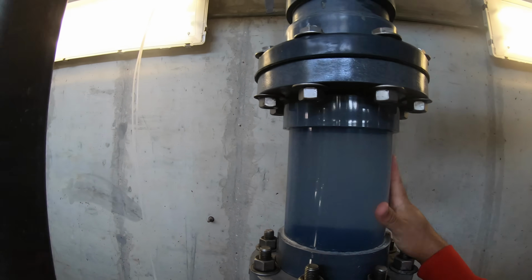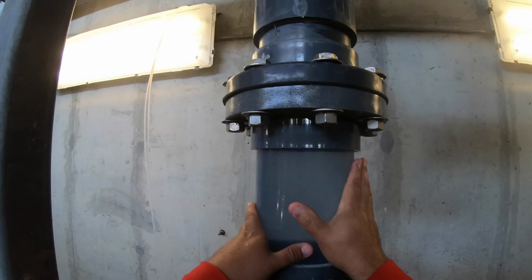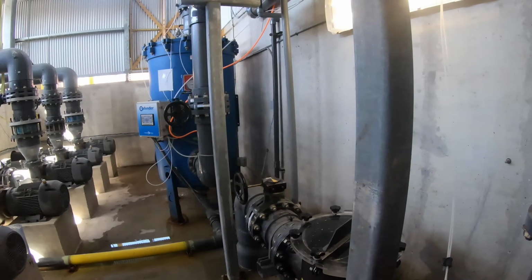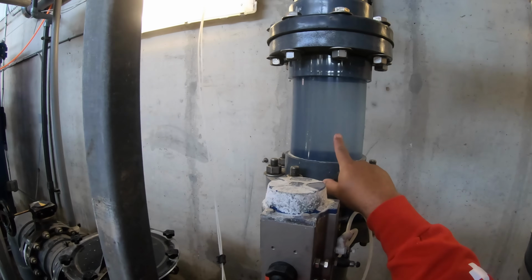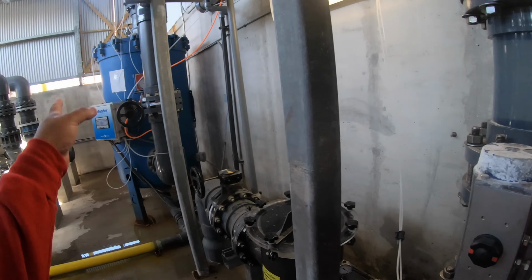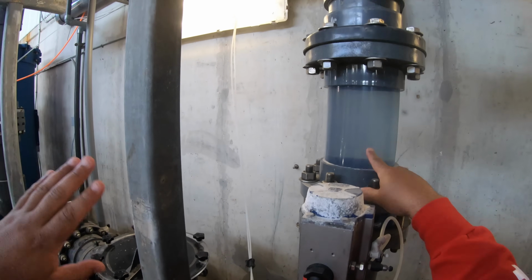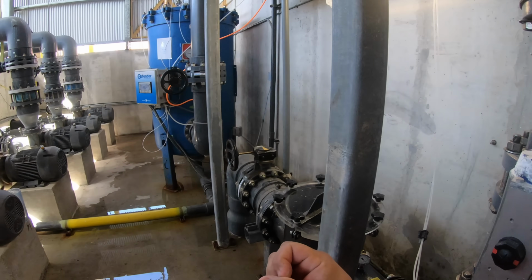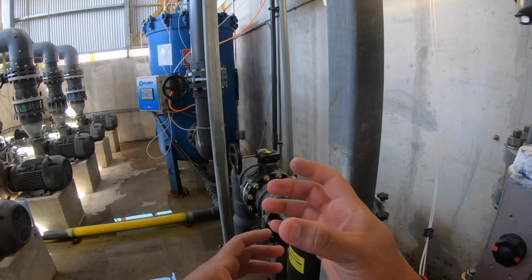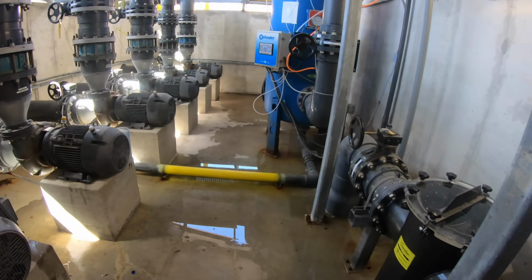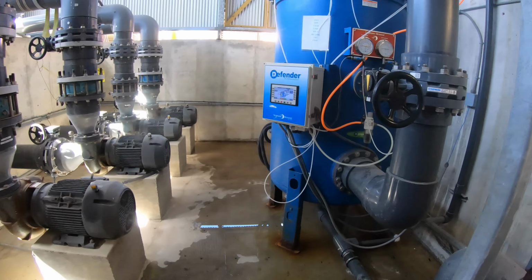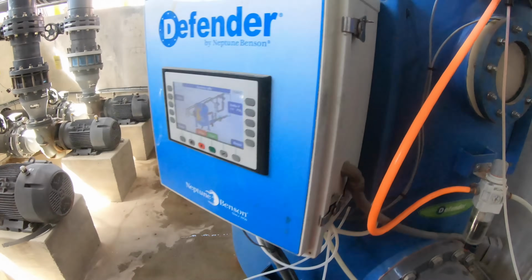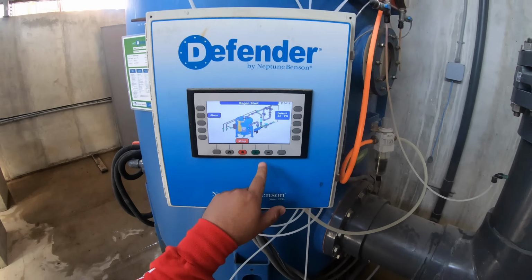So if you remember, this is one of the pipes that blew up last year that we had to work on, that I worked on. You're gonna actually see the media pass through here. So that's why we don't send it directly to the pool right now, because it's in solution. Over time, it's gonna build up onto the tubes, and that's going to make the filter bed. This is what we call the pre-coat, okay? So let's get in pre-coat. You can see it's all white. So the media is in solution, it's in water.